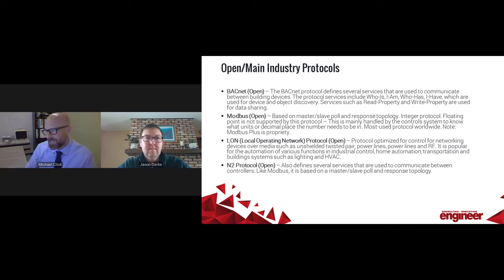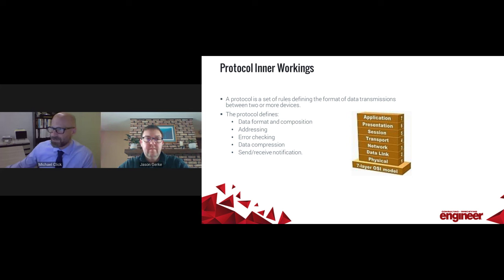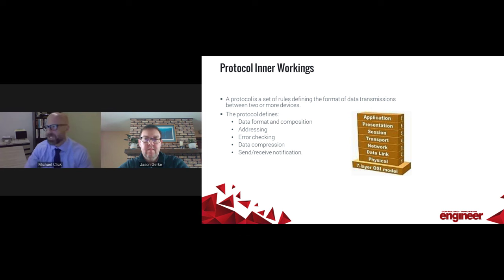Some of the advantages BACnet has: it communicates across multiple subnets, creates multi-campus control systems for campus operators, utilizes the benefits of fiber and gigaethernet, and assigns IP addresses to devices making them web accessible. The protocol interworkings operate on the OSI — Open System Interconnection — model. Goals include the ability to communicate directly with peer devices on their network, use local broadcasts received by all peers, send remote broadcasts to devices on different network numbers, and global broadcasting.